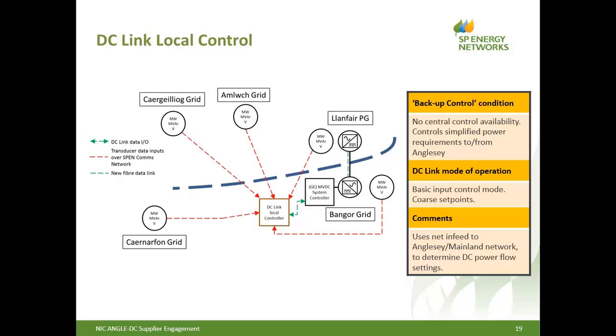So this will come into play when we've got no central control availability. It's got independent comms, it's got independent transducers, and it feeds into a local controller, which I'll call a black box with a control algorithm in it, which has a limited number of inputs but provides sufficient coarse control that we don't lose the asset should we lose the central control system or communication lines.